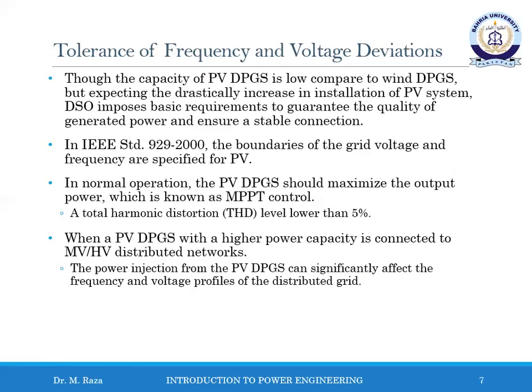The grid code says that in normal operation, the PV distribution generation system should maximize the output power, which is known as maximum power point tracking control, and the converter system interfacing the PV system with the grid must have a total harmonic distortion level lower than 5%. When a PV distribution power generation system is installed with a higher power capacity in a medium voltage to high voltage distribution network, the power injection from the PV distribution generation system can significantly affect the frequency and voltage profile of the distributed grid.